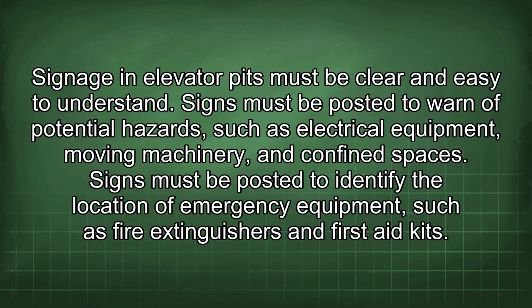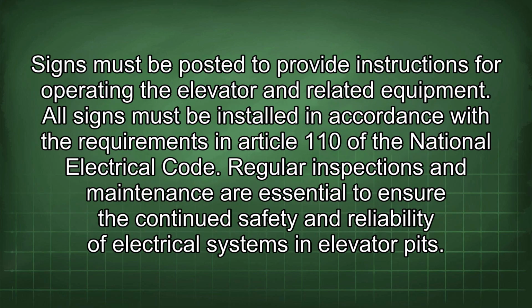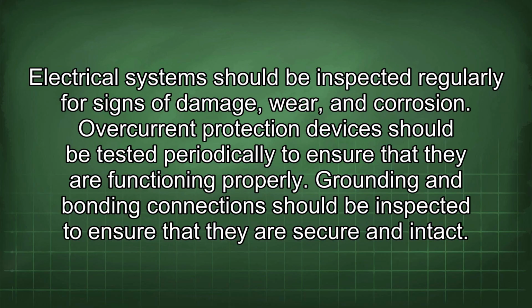Signs must be posted to identify the location of emergency equipment, such as fire extinguishers and first aid kits. Signs must be posted to provide instructions for operating the elevator and related equipment. All signs must be installed in accordance with the requirements in Article 110 of the National Electrical Code. Regular inspections and maintenance are essential to ensure the continued safety and reliability of electrical systems in elevator pits. Electrical systems should be inspected regularly for signs of damage, wear, and corrosion. Overcurrent protection devices should be tested periodically to ensure that they are functioning properly.